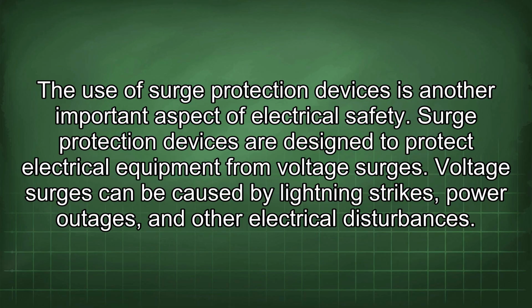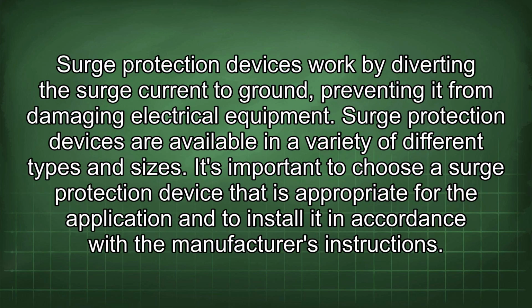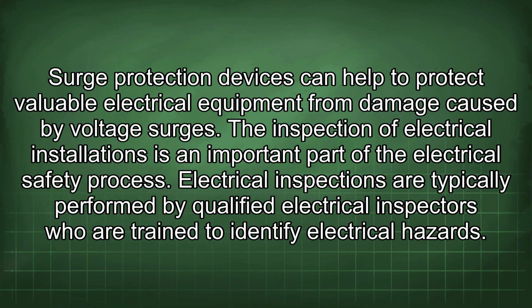The use of surge protection devices is another important aspect of electrical safety. Surge protection devices are designed to protect electrical equipment from voltage surges. Voltage surges can be caused by lightning strikes, power outages, and other electrical disturbances. Surge protection devices work by diverting the surge current to ground, preventing it from damaging electrical equipment. Surge protection devices are available in a variety of different types and sizes. It's important to choose a surge protection device that is appropriate for the application and to install it in accordance with the manufacturer's instructions. Surge protection devices can help to protect valuable electrical equipment from damage caused by voltage surges.